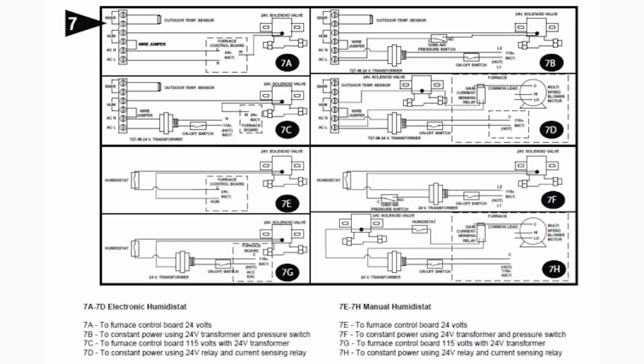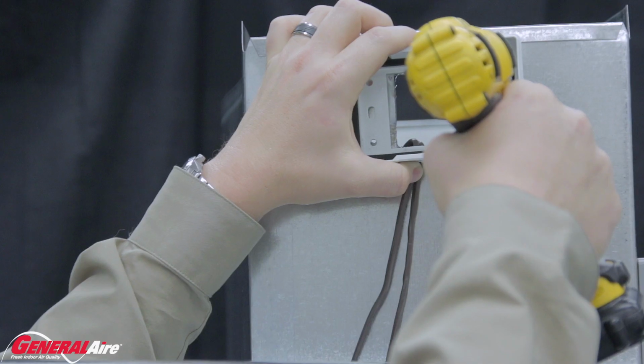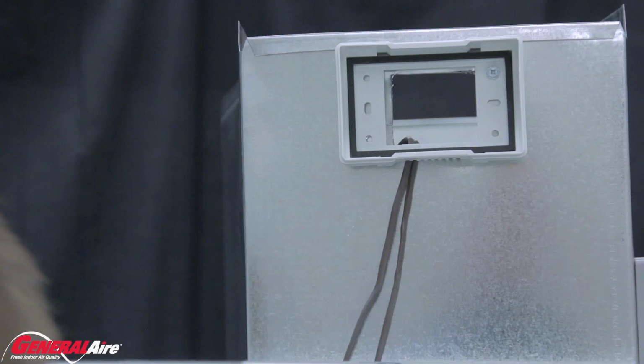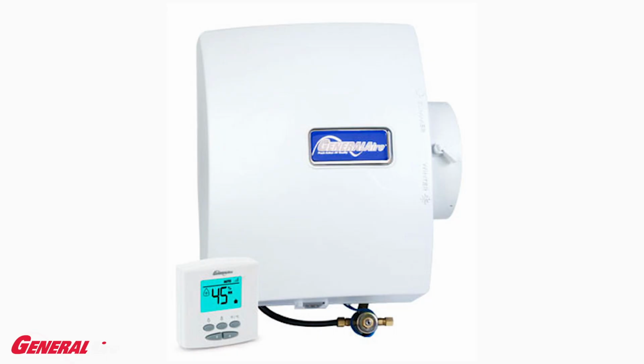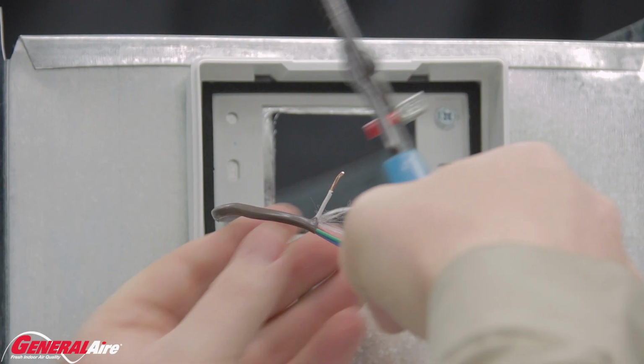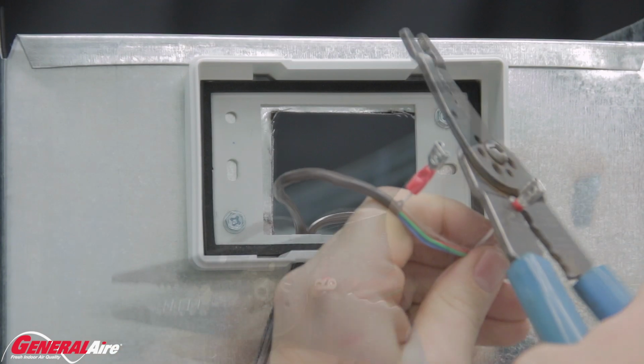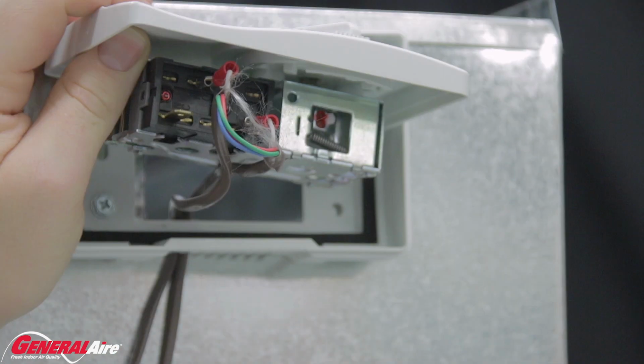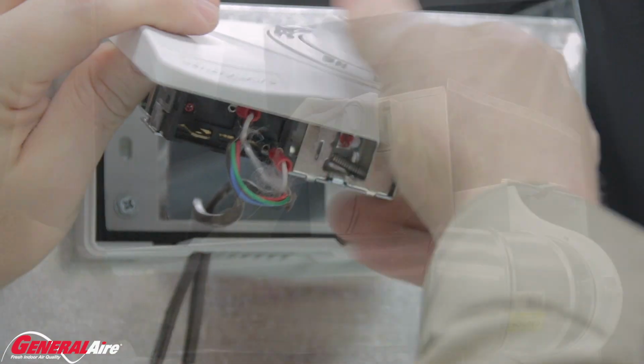Next is wiring. Use the installation manual to select the wiring diagram applicable to the humidifier you are installing and the furnace in the home. When the wiring inside the furnace is completed, run the Humidistat wire from the furnace past the solenoid and to the MHX3C Humidistat. Affix the mounting plate on the furnace using included sheet metal screws. If you are installing the GeneralAire 900A with the GFX3, please refer to the video demonstrating how to install the GFX3 Humidistat. Install the wiring to the Humidistat using the common C and normally open NO terminals by using the included female spade terminals. Once the wiring is connected, clip the Humidistat onto the previously installed base.